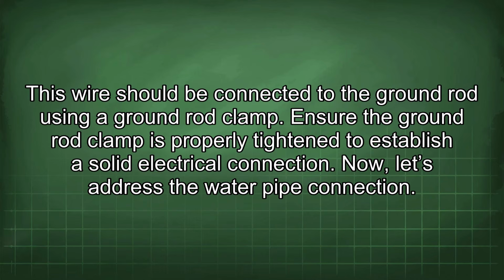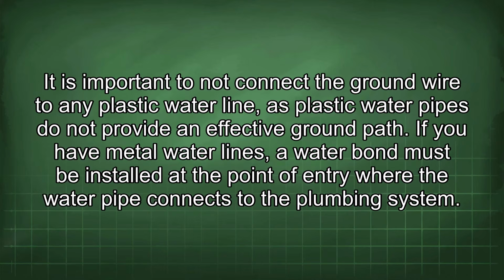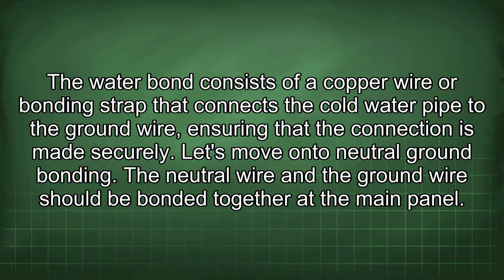Now let's address the water pipe connection. It is important to not connect the ground wire to any plastic water line, as plastic water pipes do not provide an effective ground path. If you have metal water lines, a water bond must be installed at the point of entry where the water pipe connects to the plumbing system. The water bond consists of a copper wire or bonding strap that connects the cold water pipe to the ground wire, ensuring that the connection is made securely.